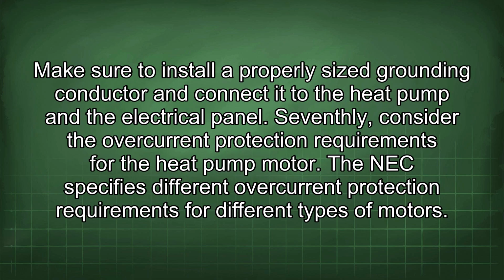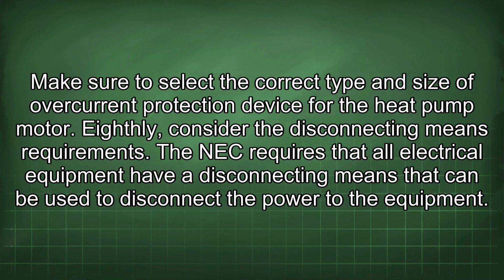Make sure to install a properly sized grounding conductor and connect it to the heat pump and the electrical panel. 7th, consider the overcurrent protection requirements for the heat pump motor. The NEC specifies different overcurrent protection requirements for different types of motors. Make sure to select the correct type and size of overcurrent protection device for the heat pump motor.